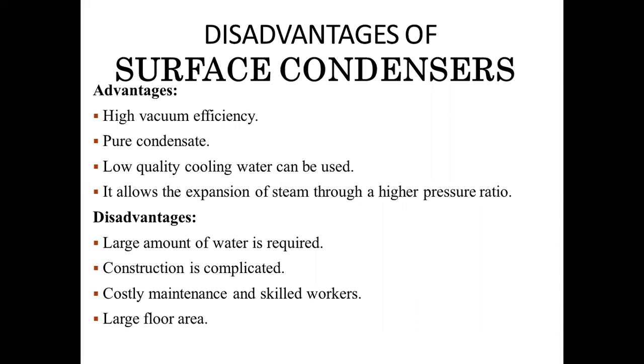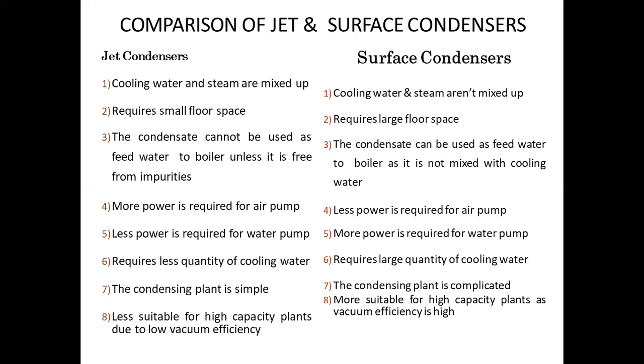Now there are some advantages and disadvantages of the surface condenser. If we are talking about the advantages, there is very high vacuum efficiency. Condensate is in the purest form. Low quality cooling water can be used. It allows expansion of steam through a high pressure ratio. But there are some disadvantages also: a large amount of water is required for cooling the steam. Construction is complicated, it is very costly, maintenance is costly, skilled workers are required, and it needs a large surface area.